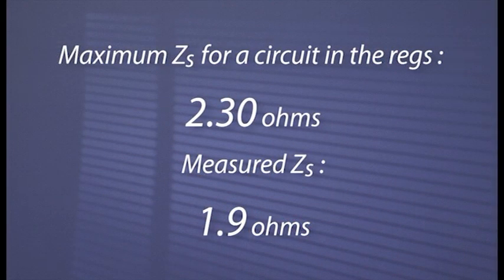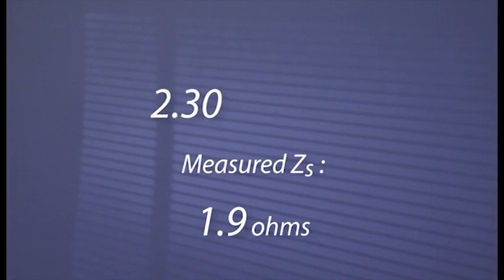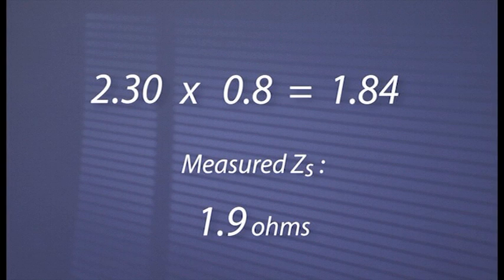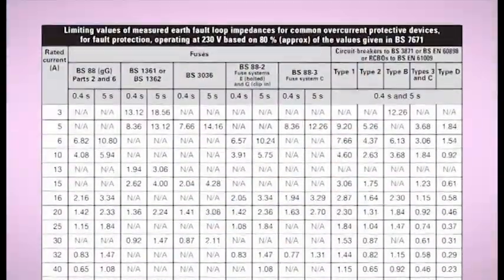For example, if the maximum ZS for a circuit in the regs was 2.3 ohms and the measured ZS was 1.9 ohms, on the face of it everything seems fine. But reduce the maximum allowed ZS to 80% of its value and you get 1.84 ohms, which tells us we have a circuit which may not achieve the required disconnection time of 0.4 of a second in the event of a fault. Don't forget that all the NIC certificate and form pads have the 80% values on the inside front cover. These values are used for comparison when testing, but not to be recorded on the certificate or report forms.